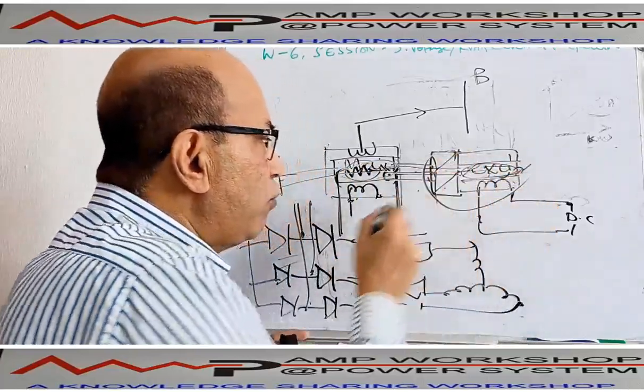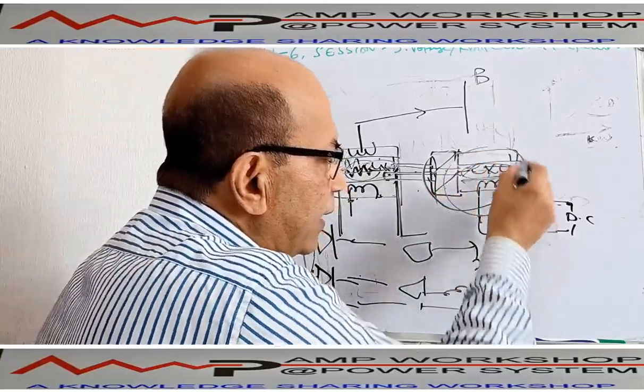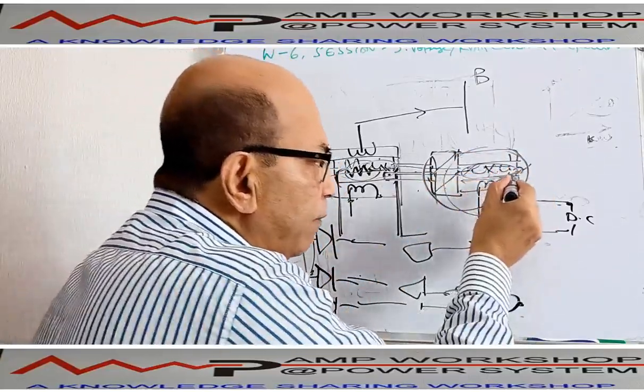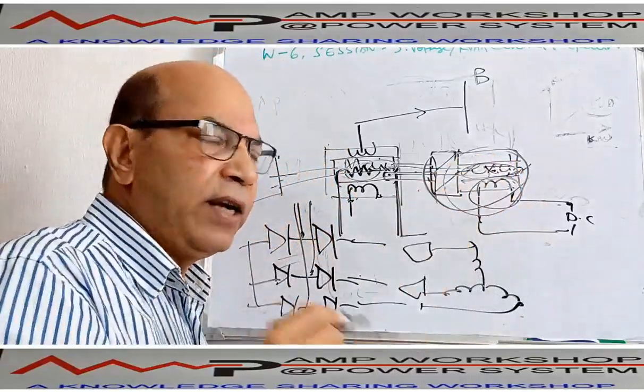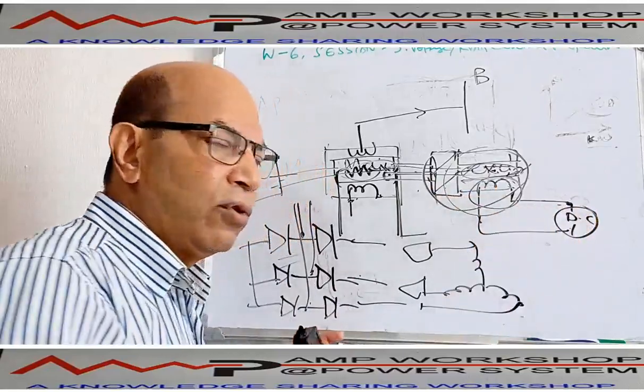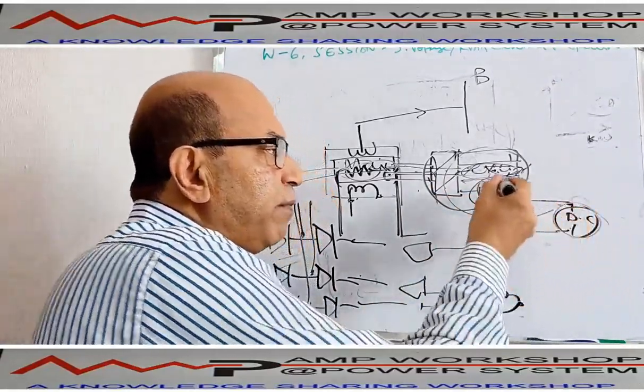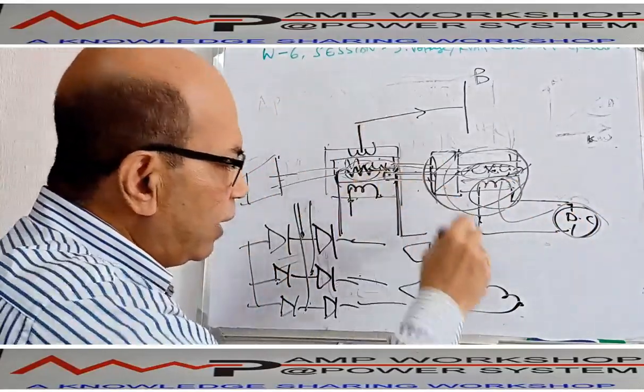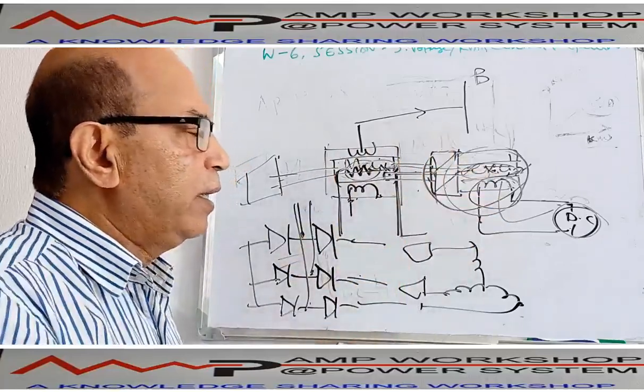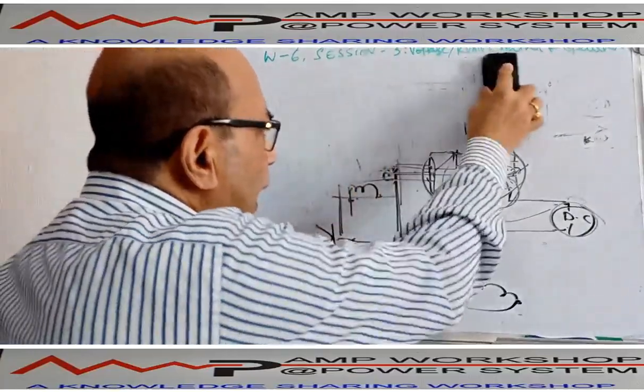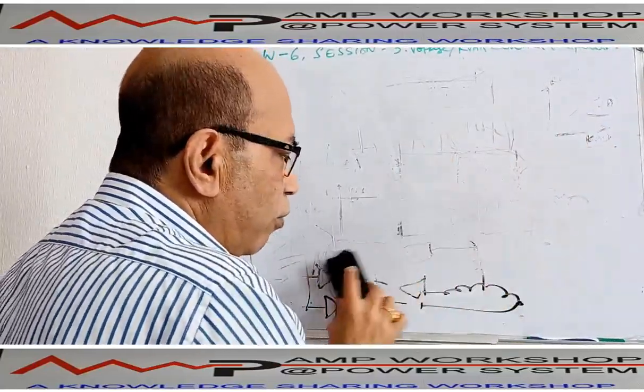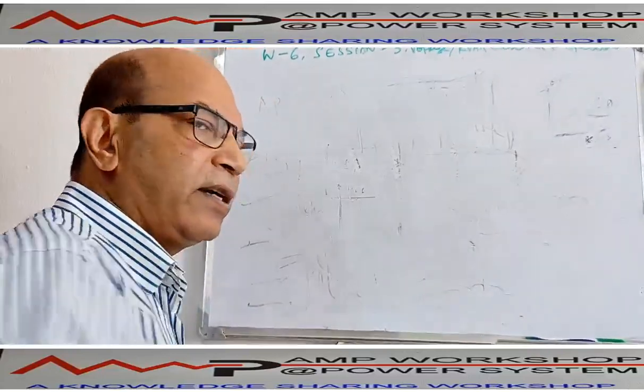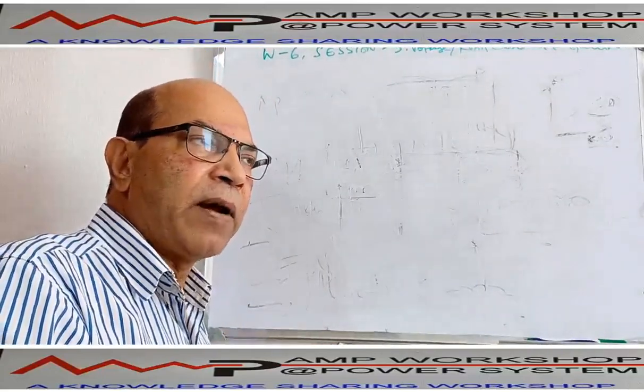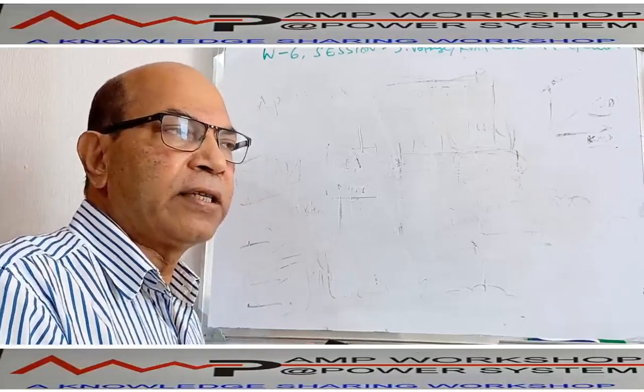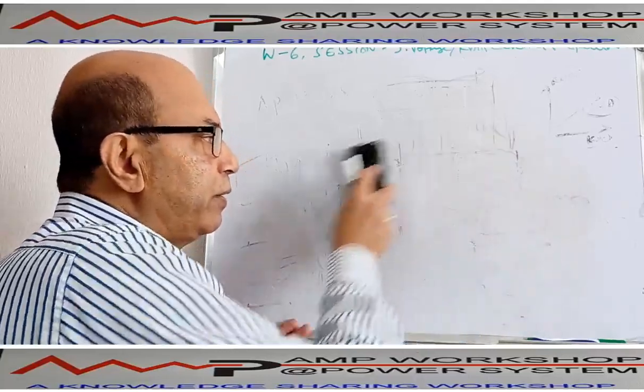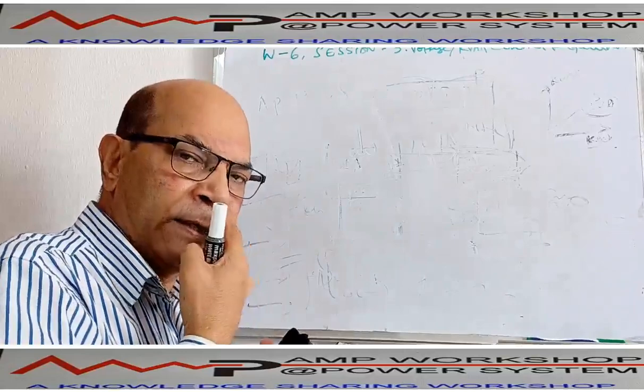So when you want to control the generator voltage, we have to control the exciter voltage. How do we control the exciter? This part we cannot control. Only the exciter field current we can control, by this DC supply. So the AVR's job is to change this DC supply to the field winding to control the generator voltage. So this way the generator is operating. Now we can describe in more detail how the generator voltage can be controlled. We have to control the exciter field winding supply, which is a DC supply. How we will control this part is the discussion today.